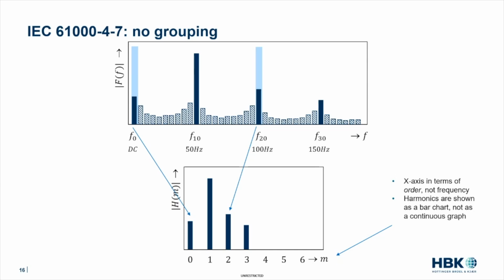And what you also see, if you have looked at spectral images, those are normally a bit squiggly lines. But in harmonics, it's customary to display the harmonics as a bar chart, which is done at the bottom of this page. And it's also no longer customary to put the frequency on the horizontal axis, but it's more common to put the number of the harmonic. So the first harmonic and the second harmonic, etc. So that is common. But just to summarize, when you are using no grouping, you are only using the frequency components at 0 Hertz, 50 Hertz, 100 Hertz, 150 Hertz, etc. So that is the flavor no grouping.